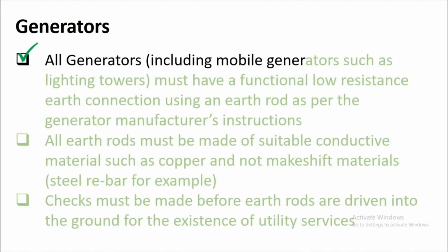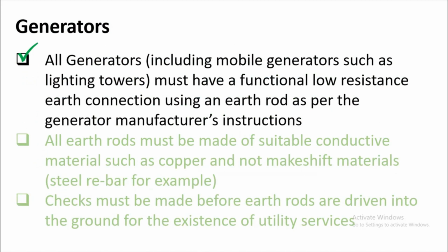Generators, all generators including mobile generators such as lighting towers, must have a functional, low-resistance earth connection using an earth rod as per the generator manufacturer's instructions. So, if you have generators, even if mobile or static, including the tower lights, make sure there are provisions for earthing on that equipment. Make sure there are earth rods that the user can drive into the ground, so that he can connect the green-yellow cables as earthing to the earth rod. And of course, you need to consult the manufacturer's instructions on how to install it. So again, this should be done by competent persons.